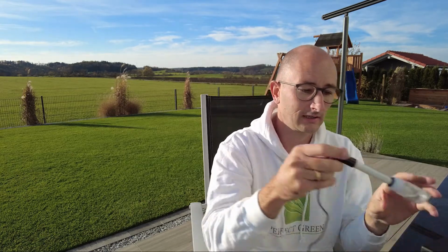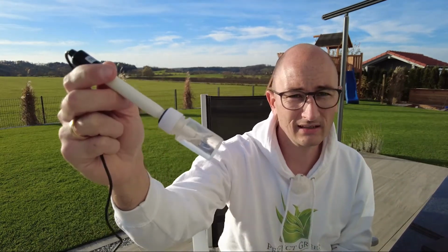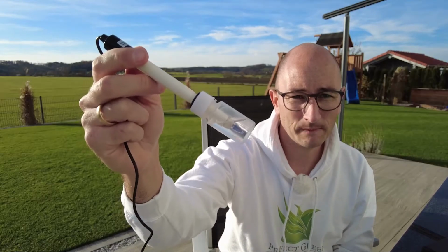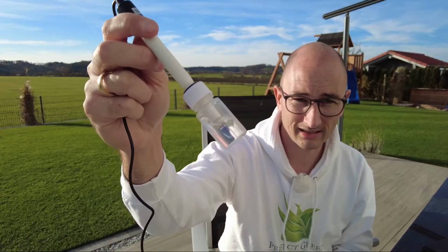Now we come to the first disadvantage. You must be clear that the device is a high performance measuring device, and that is why it is extremely sensitive. That is why the measuring probe here always has to be in the storage solution. That is really important so that nothing breaks and you don't get false values.